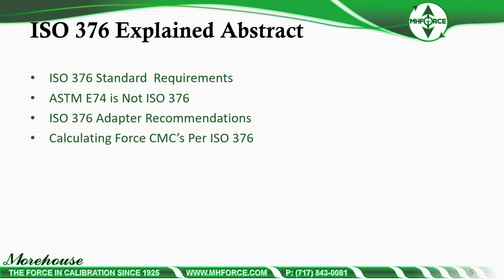The standard does a fantastic job in the annex of recommending good adapters for force measurement. That's something I'm very, very passionate about, because you can do all the right things, and if you fail to get the adapters right, there are going to be errors. In some cases, those errors are 20 times higher than your expected calibration result, just from switching top pads, using the wrong pins, doing things that are not what the lab did during calibration. When we do a calibration, we hope to replicate how the customer is using the instrumentation. If we fail to do that, and the customer fails to use the instrument the way we said we calibrated it, there are very, very large errors. ISO does a fantastic job at the end, which we will talk about, of diving into those and trying to ensure that results are repeatable.